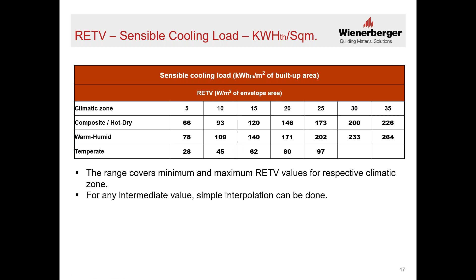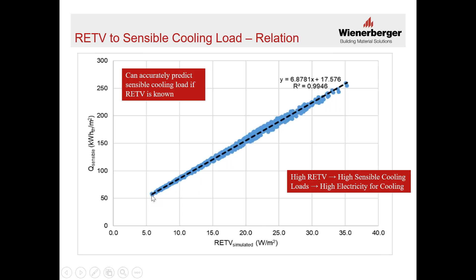Hence, we see that there is a difference as the RETV progresses in numbers. The sensible cooling load required to cool the indoors goes on increasing, the maximum being in warm and humid, up to 264. These values can be interpolated within the table to obtain the sensible cooling load, also to calculate payback and the cost we save. If we know the RETV accurately, we can accurately predict the sensible cooling load. Higher RETV values mean higher sensible cooling load, lower RETV values mean lower sensible cooling load. For around 7, the sensible cooling load is around 51, 52, quite low as compared to here.